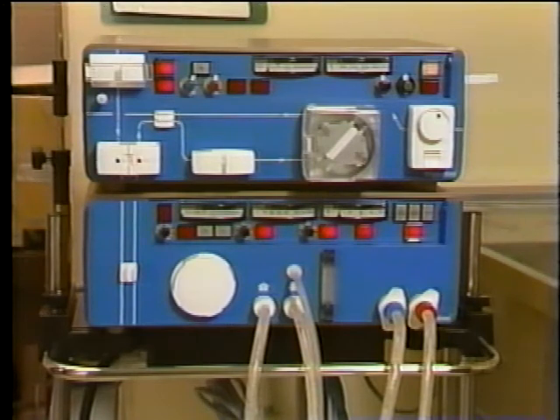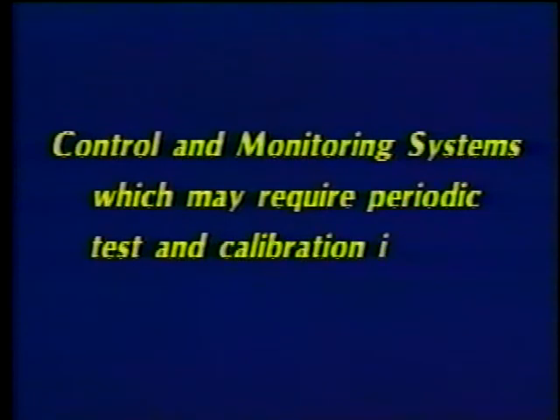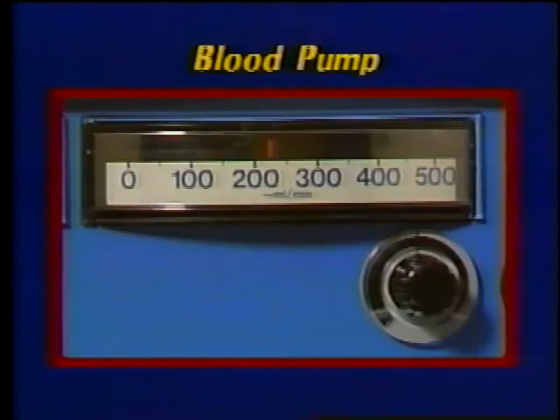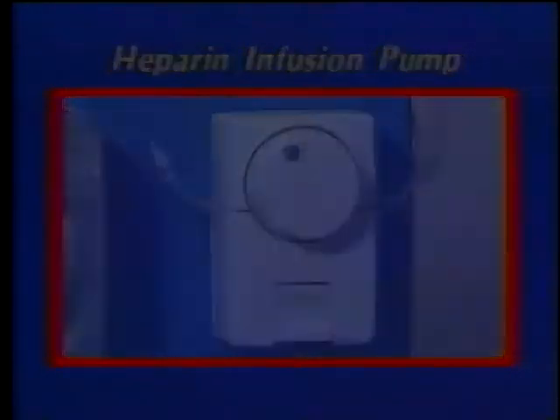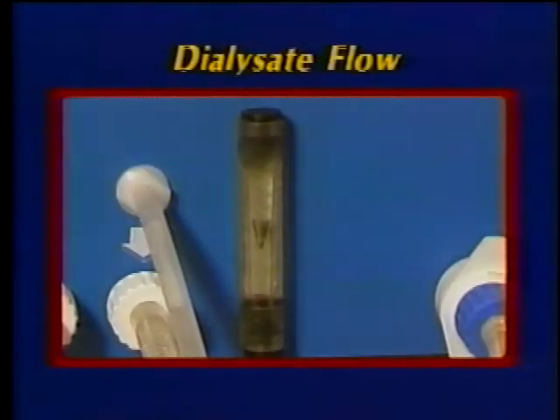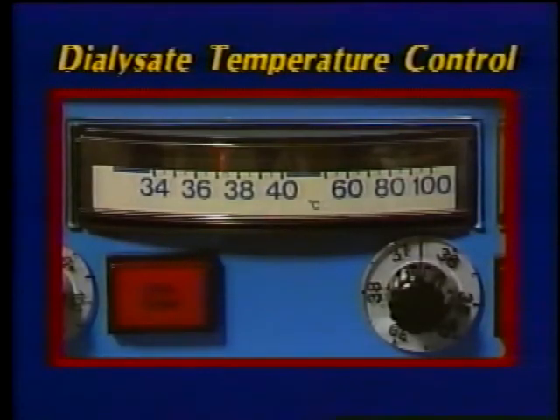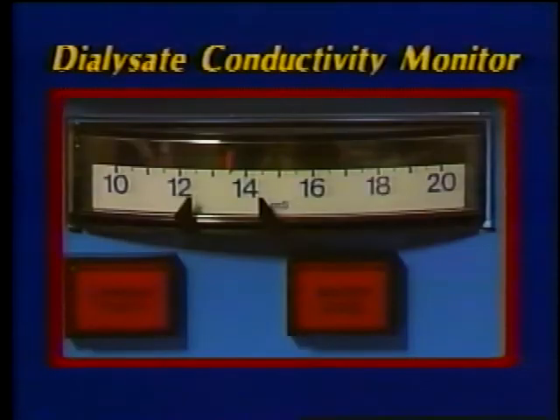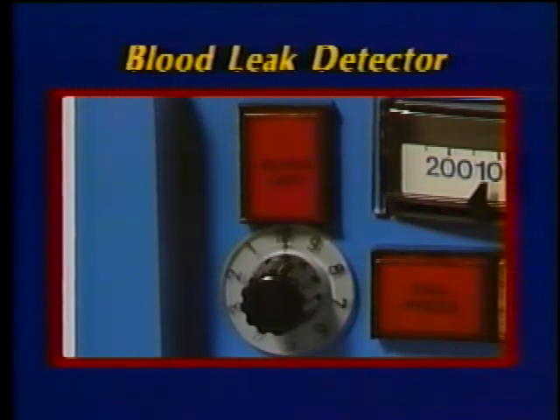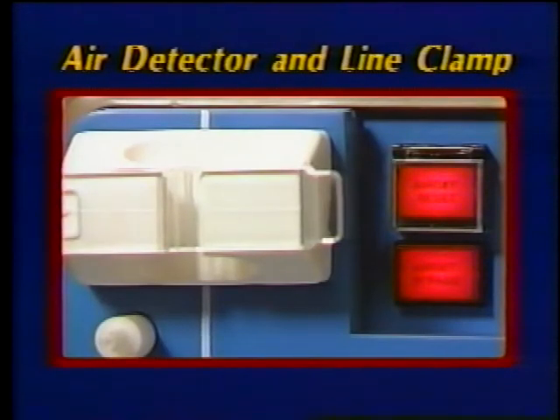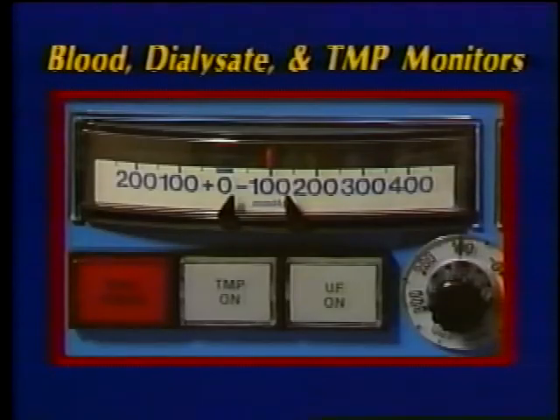All manufacturers recommend that some functions on the equipment be checked or calibrated periodically. Control and monitoring systems which may require periodic test and calibration include blood pump, infusion pump, dialysate flow, dialysate temperature control, dialysate conductivity monitor, blood leak detector, air detector and line clamp, and finally, the blood, dialysate, and transmembrane or negative pressure monitors.